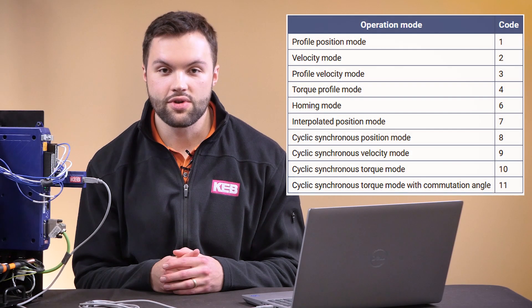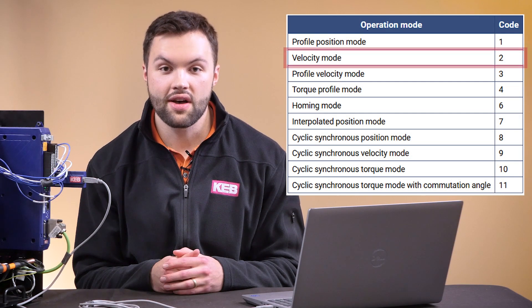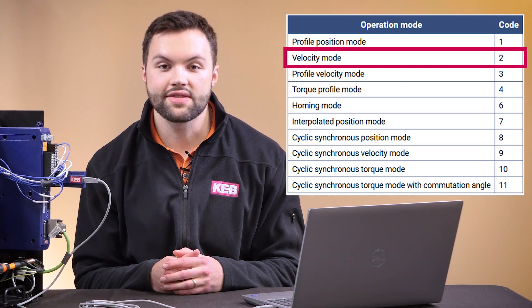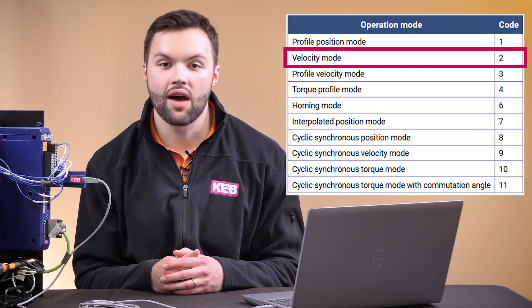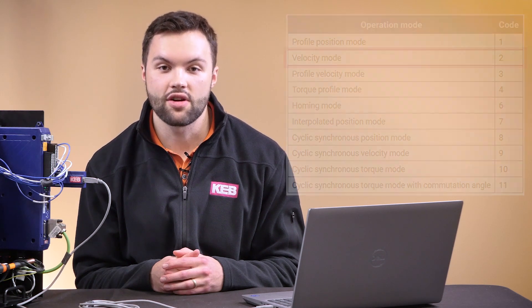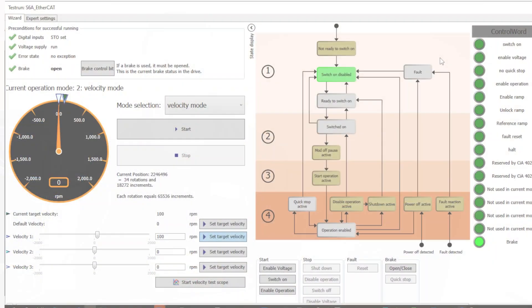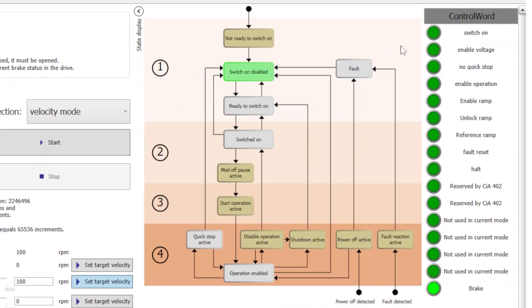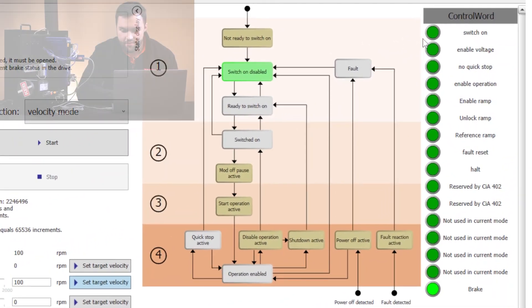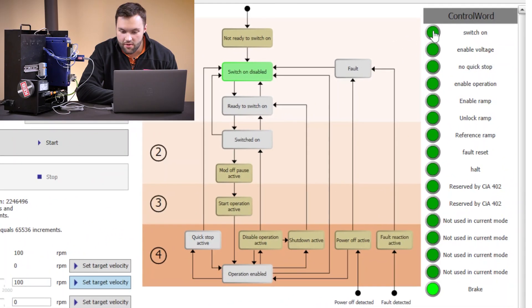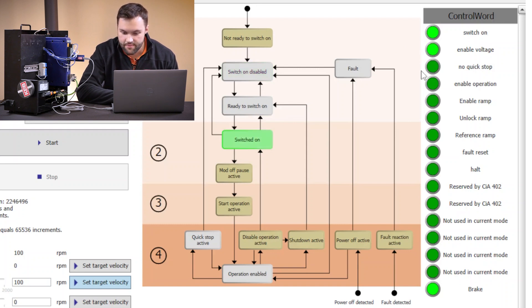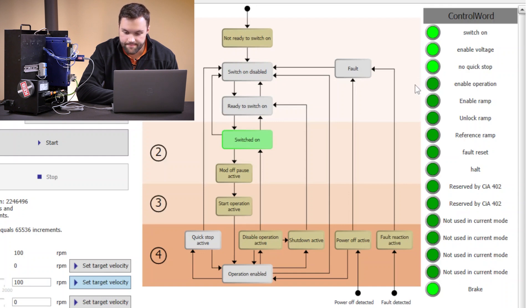To demonstrate the control word and the state machine in velocity mode, we will be using the test run wizard in Combivis 6, our drive software. Looking at KEB's Combivis 6 software, we can enable the switch on bit in the control word column. We can enable voltage, enable the no quick stop bit, and enable operation.